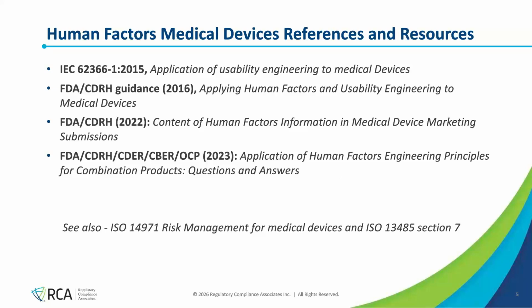So from a high level, what we're going to talk about today is covered largely in these standards and guidances, namely 62366, which is the application of usability engineering to medical devices, which does cover the entire process and the contents of an HFE file. But the FDA has also released several guidances associated with human factors or usability that will also be touched on while we go through this today. It's worth noting, however, that 62366 and the FDA guidances also tie this process into a 14971 risk management process and risk management file, as well as your 13485 design and development files. So those two things should not be left segregated on their own.